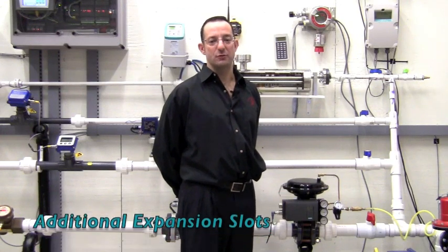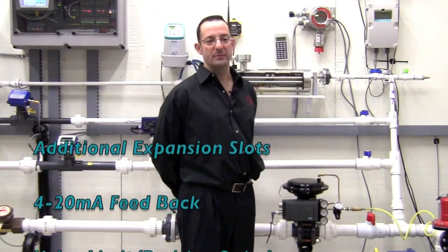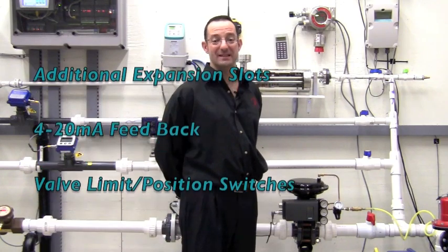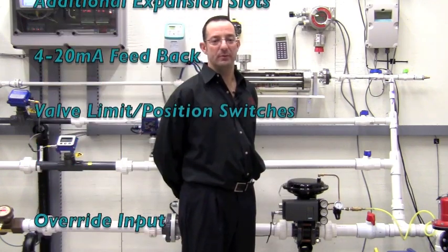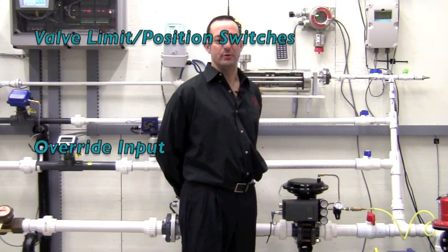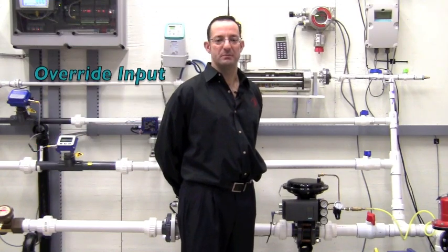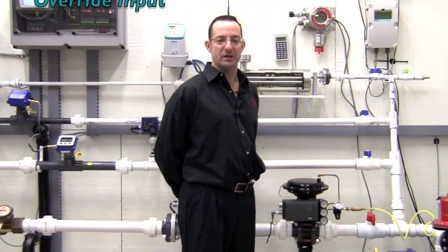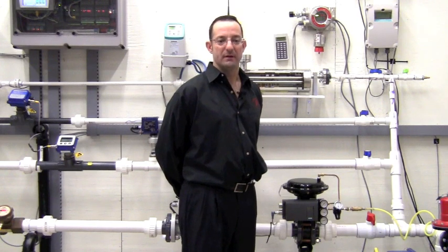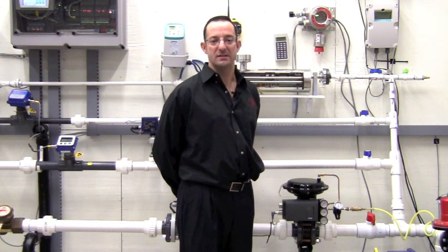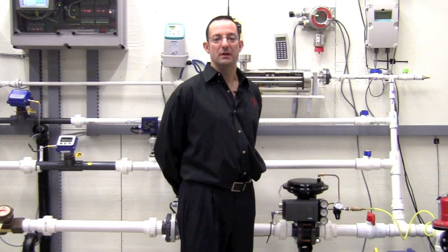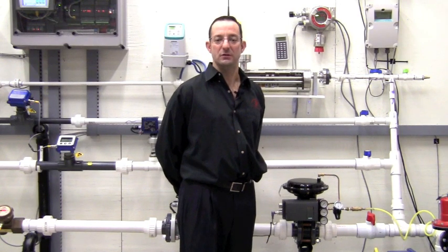Want 4 to 20 milliamp feedback for true valve position? Or limit switches that are completely isolated and independent of the current loop? How about an override input to force the positioner to a given position, such as in a combustion control system? The PS2 has expansion slots to accommodate these boards, which will give you the functionality you want.